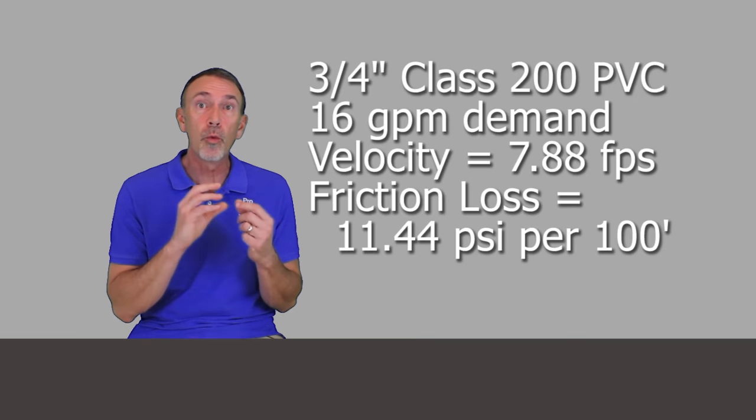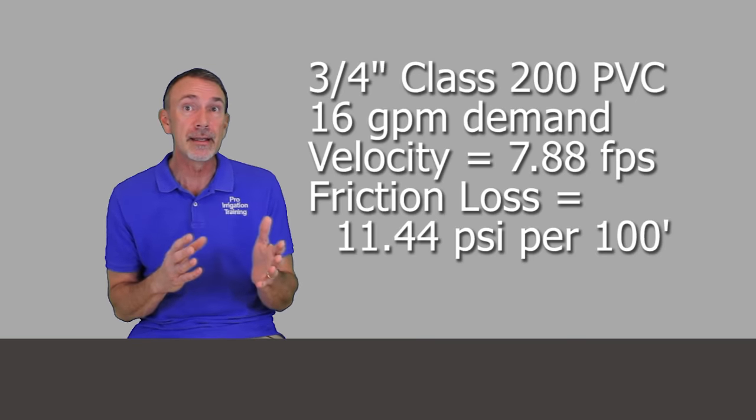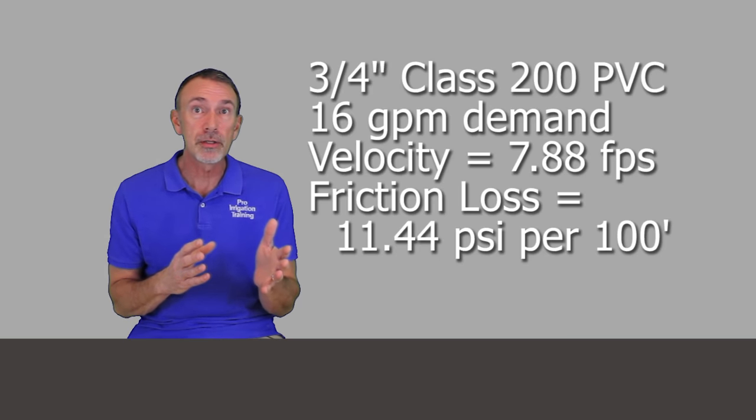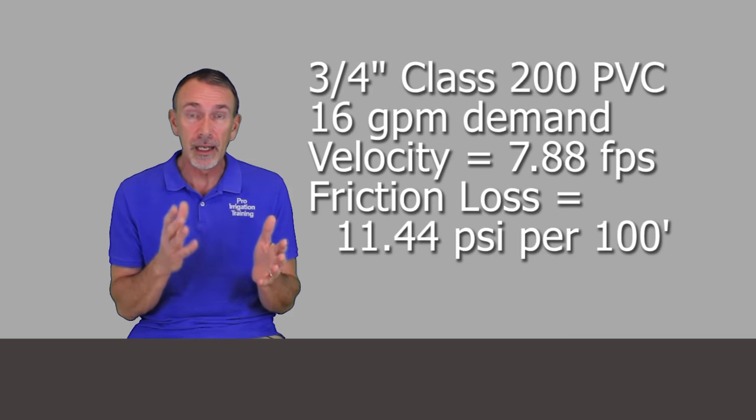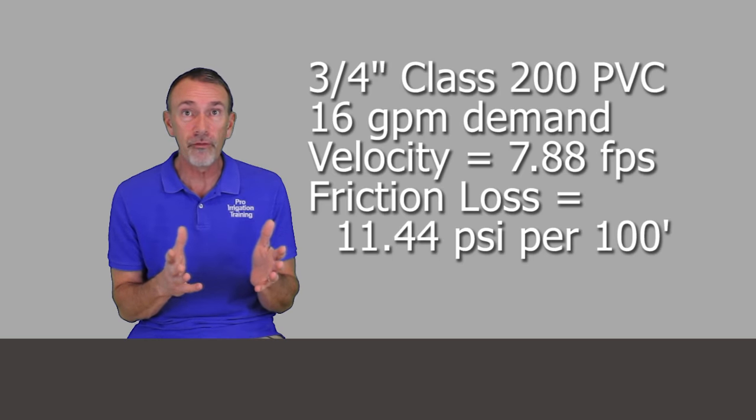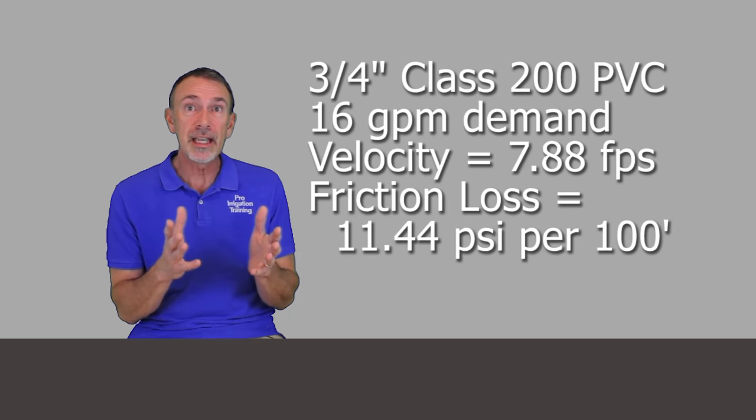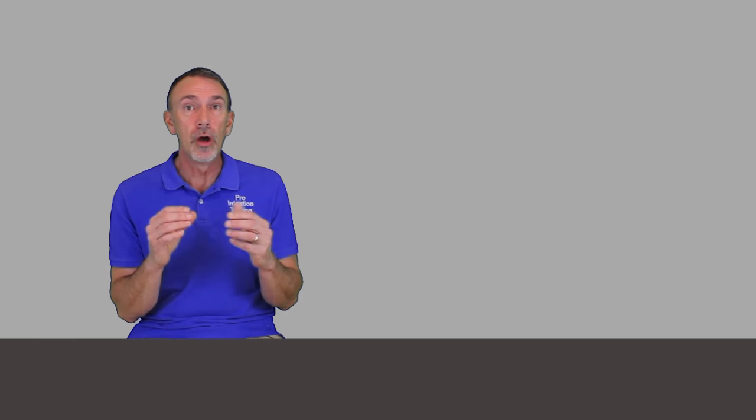The friction loss on that is 11.44 pounds per square inch per 100 feet of pipe. So 3.38 psi loss per hundred feet in the one inch pipe versus 11.44 loss in the three-quarter inch pipe. That should tell you that going down a size of pipe is going to harm the system, not help it. It's not going to add pressure to it, it's going to take pressure from it. It's going to cause water to move faster through the pipes to try to deliver the same demand and it's going to rob energy out of that line.